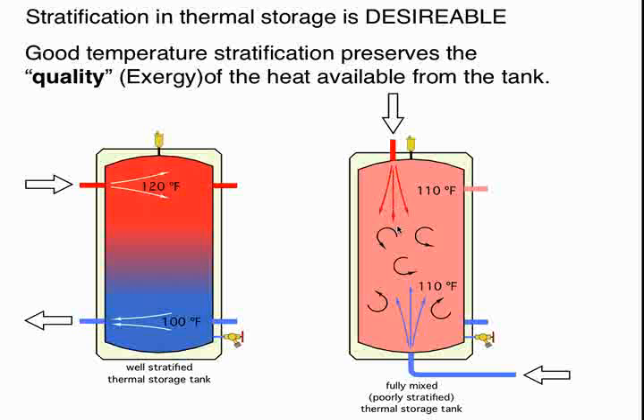One is to have a vertical flow jet by creating a vertical inlet pipe in the top of the tank. And these red arrows would represent hot water that's basically being pushed down. Imagine taking a garden hose and just putting it down into the top of a 5-gallon pail filled with water. You know you're going to get a stirring action inside that pail, and you would get something similar inside the tank. So we don't want to do this. Neither do we want to do this, a return pipe that comes up into the bottom of the tank. And this is a common error, and I'll show you a couple systems. But however we've stirred that tank up, we've got the tank at a uniform temperature of 110 degrees Fahrenheit.